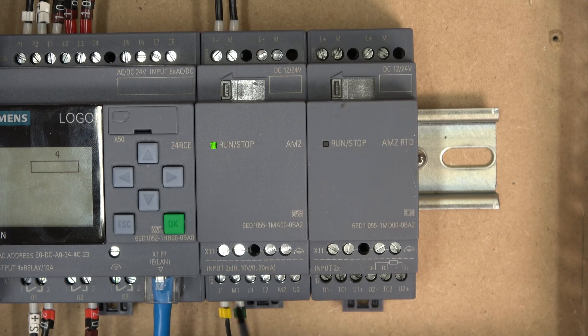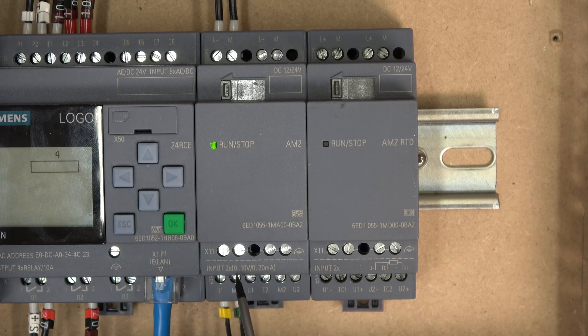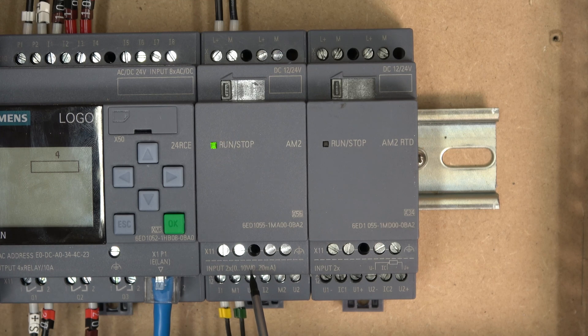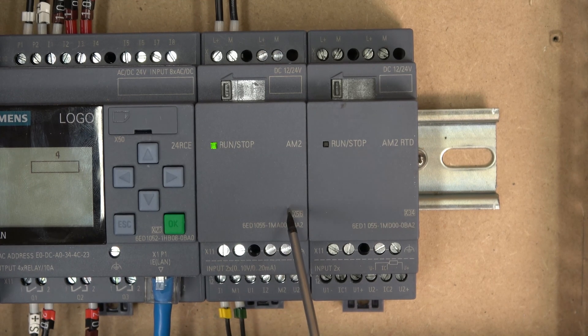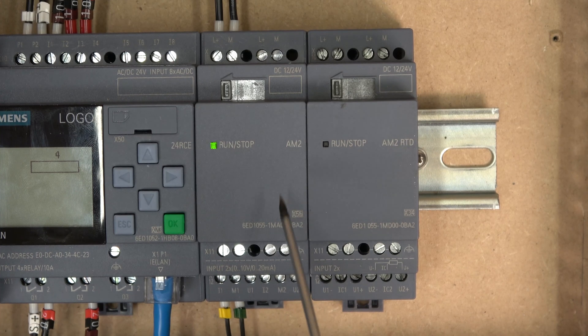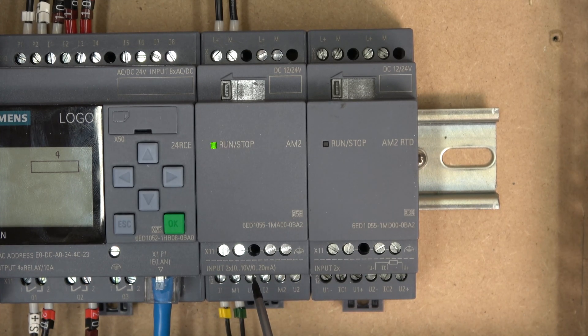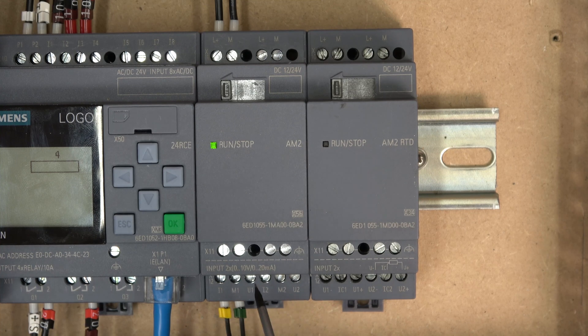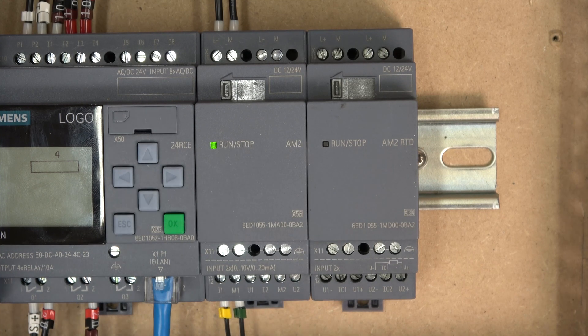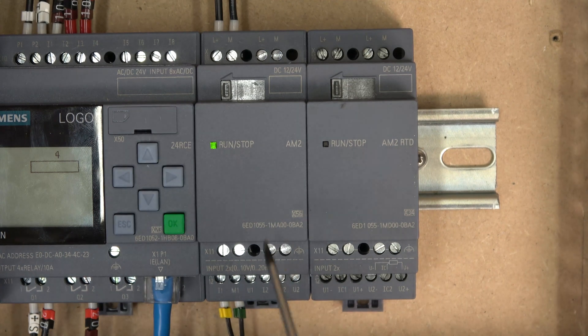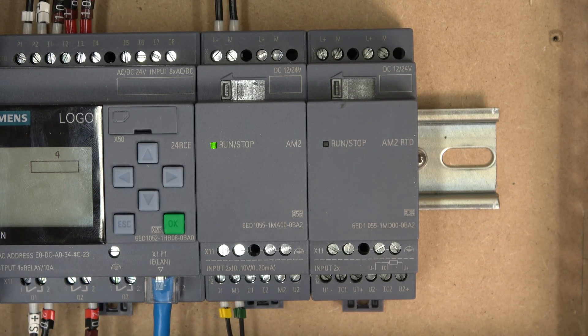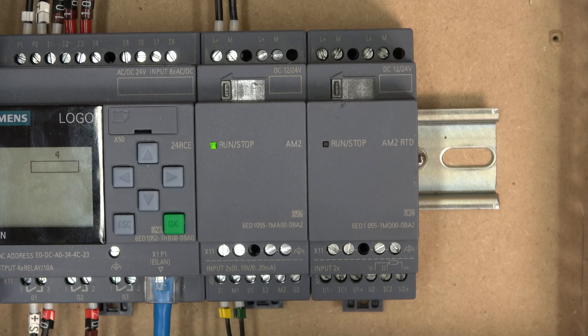So as you can see, you have two channels in here. You get 0 to 10 volts or 0 to 20 milliamps. I think the later cards do both 0 to 20 and 4 to 20. My one does 0 to 20 milliamps. And that's pretty much what there is about the wiring.